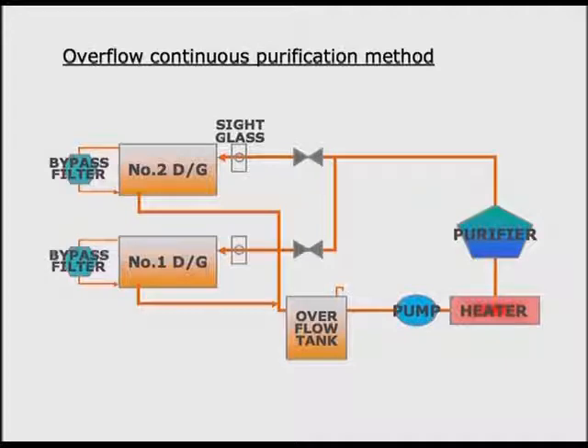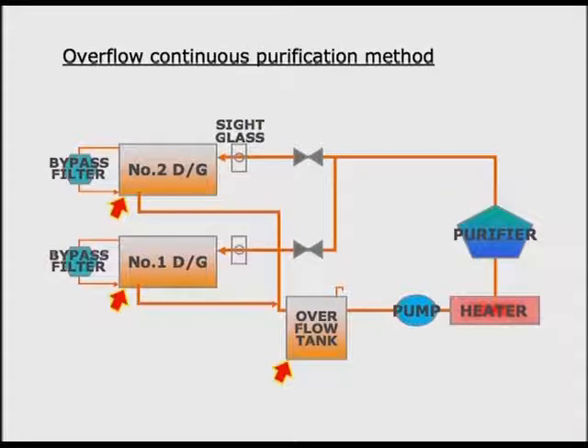The continuous overflow cleaning method allows you to curb the dirt level of the lube oil to a certain level, because it constantly cleans the lube oil during operation using its own tank. Transfer the lube oil in both the sump tank and overflow tank of the settling tank regularly to carry out cleaning of the tanks.